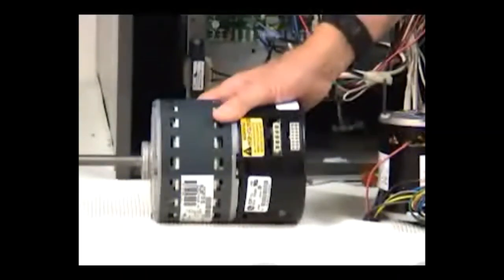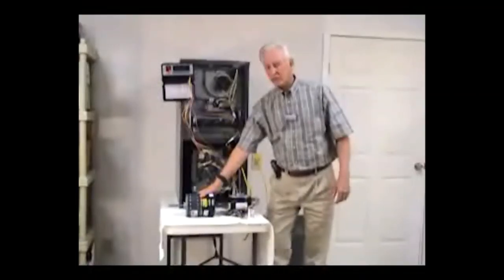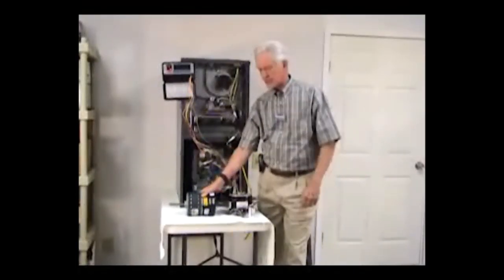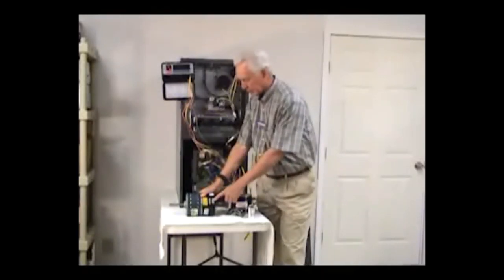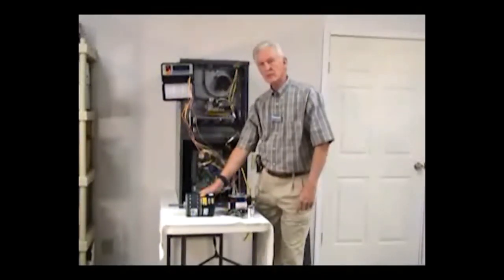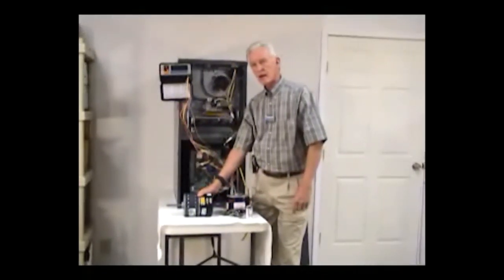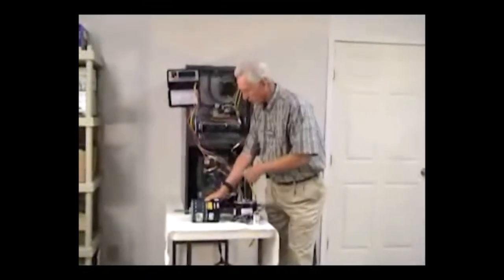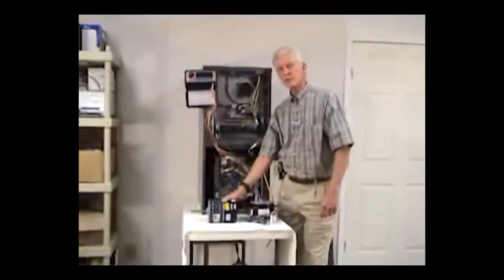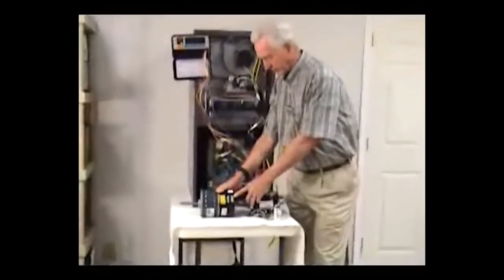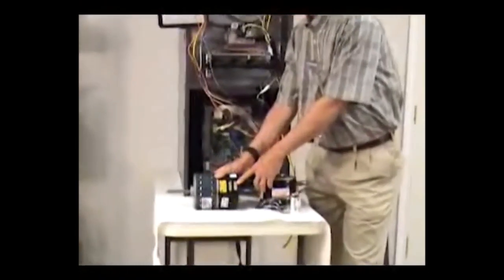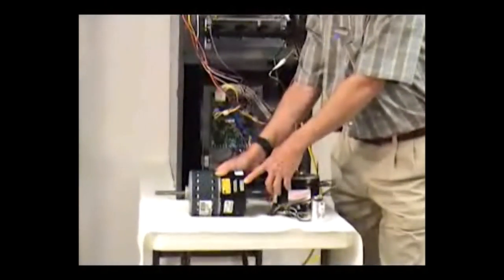And it's a three-phase motor. Okay, the module that's on the back of the ECM motor has a 16-pin connector here that will receive impulses from your board, which will also get the signals from your thermostat that will tell it what RPM it needs to run on for that specific application.